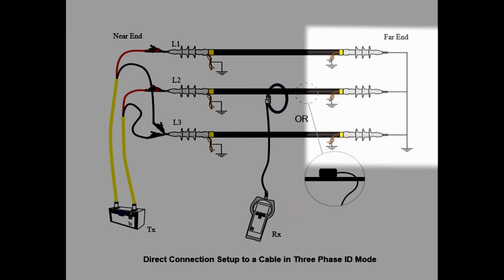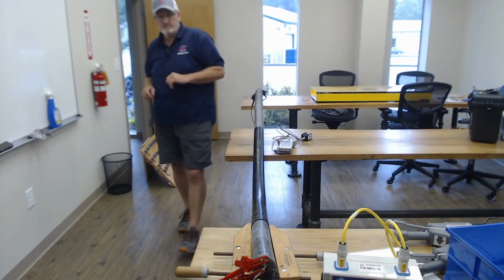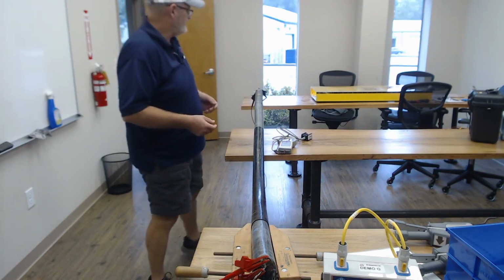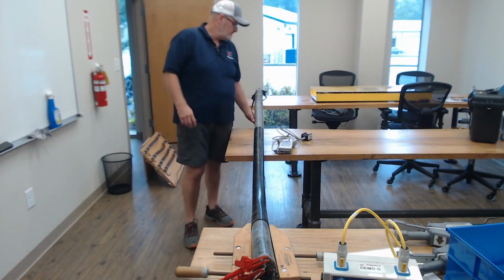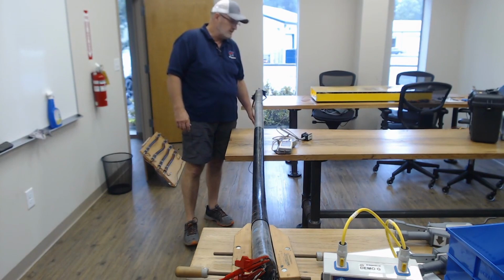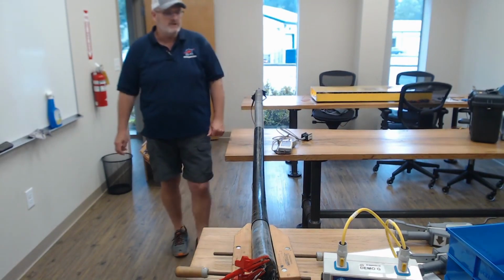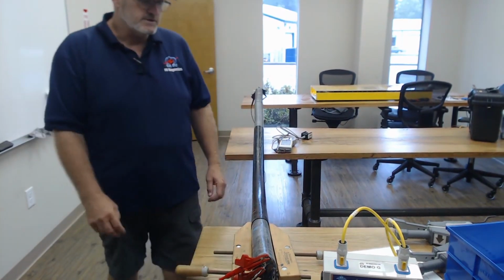If you want to take those jumpers to ground on the far end, you can do that. From a safety point of view, you can do it. You don't have to do it from an identification perspective, but it is important that A, B, and C phase are jumpered together. And then if you want to take them to ground, you can.